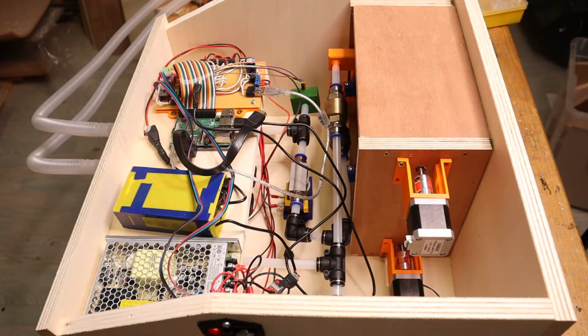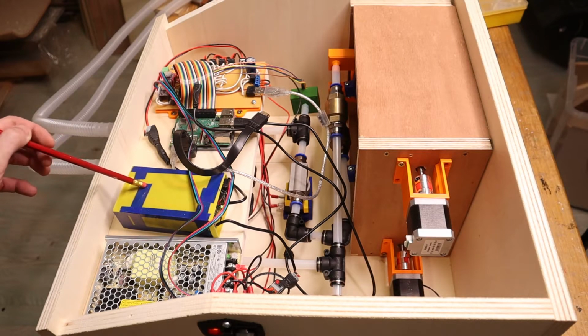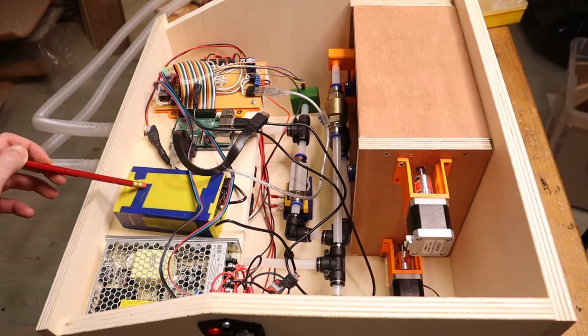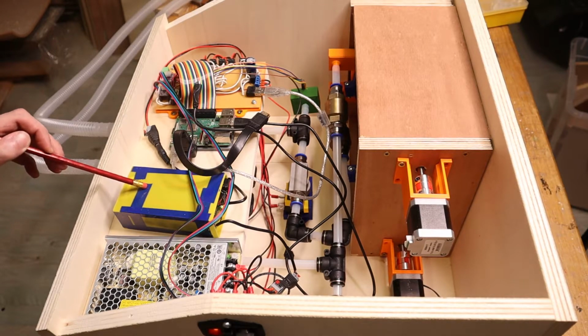With the top plate removed, we can see the four major components of the electronics section. We have the power supply, which takes the 230 volts AC and turns it into 24 volts DC. This is a Mean Well unit that can also accept 110 volts, like most units can. We have a backup battery over here, so that if the power is interrupted, the unit will still function.